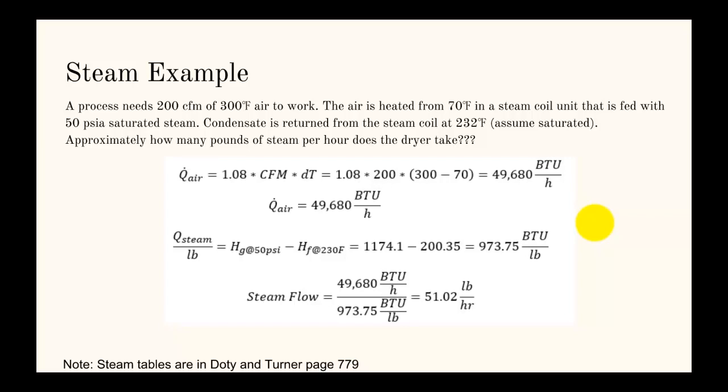The idea here is we're supplying heat to the air with the steam. The first thing we need to do is figure out how much heat we need to supply to the air. We do that by taking the formula 1.08 times CFM times delta T. Remember, this formula is very specific for air when you have a CFM air flow and a temperature change. We plug in the CFM and the temperature change, and we get 49,680 BTUs per hour. That's how much heat we have to supply.